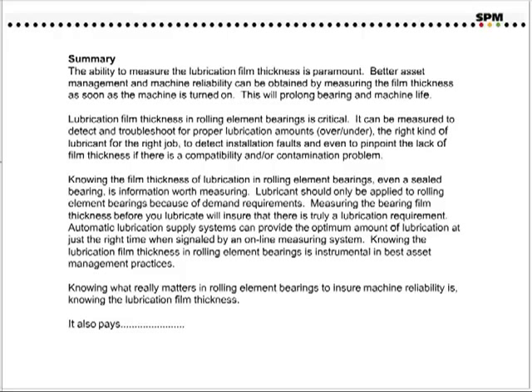Lubricants should only be applied to rolling element bearings based on demand requirements. Measuring the bearing film thickness before you lubricate will ensure that there is truly a lubrication requirement. Automatic lubrication supply systems can provide the optimum amount of lubrication at just the right time when signaled by an online measuring system. Knowing the lubrication film thickness in rolling element bearings is instrumental in best asset management practices. Knowing what really matters in rolling element bearings to ensure machine reliability is knowing the lubrication film thickness — and, of course, it also pays. Thank you.